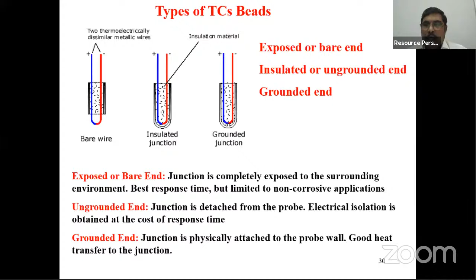Suppose you are looking for low temperature measurement, say from -50 to about a few hundred degrees Celsius, the T-type thermocouple is the best one, which has very good accuracy. The K-type thermocouple is essentially meant for high temperature applications. If you want to measure temperature from say 200 up to 1000 degrees Celsius, you opt for the K-type thermocouple. If you use the K-type thermocouple for low temperature applications, the error will be very high, more than 5 degrees Celsius. And the J-type thermocouple is meant for 0 to 200. But there is a problem with the J-type thermocouple.